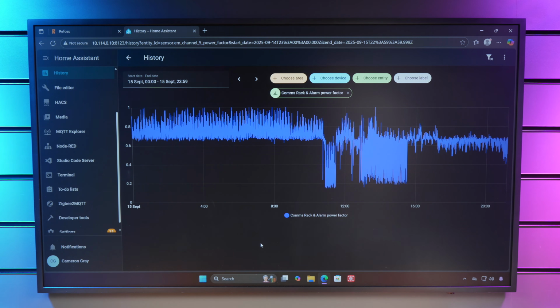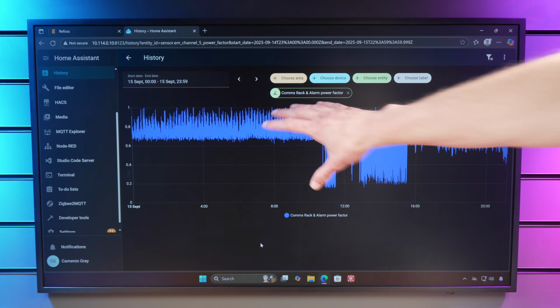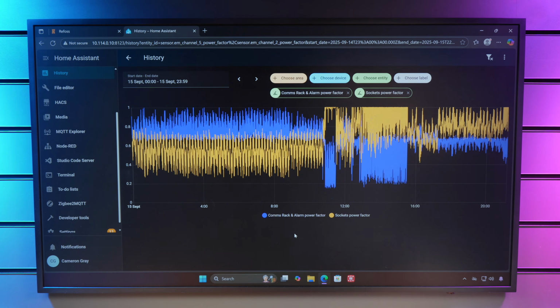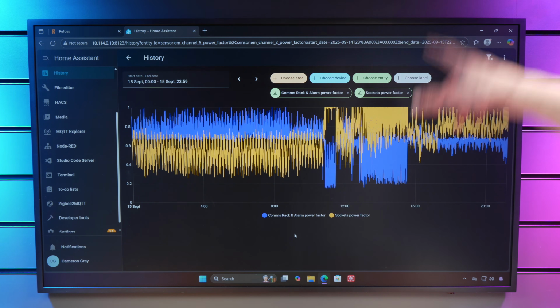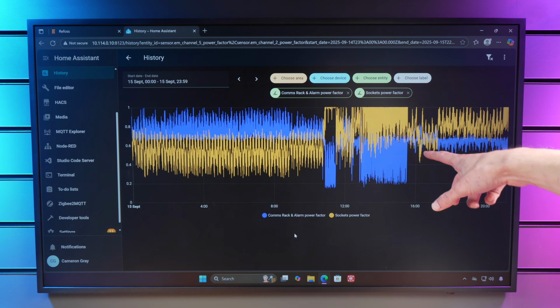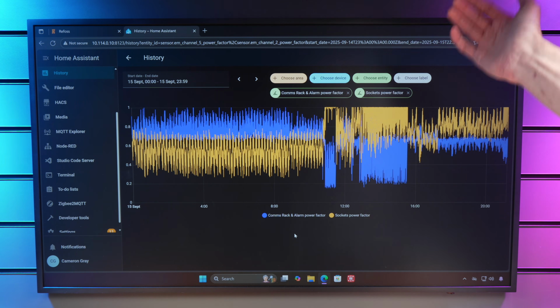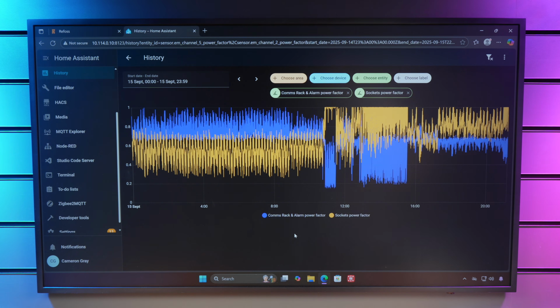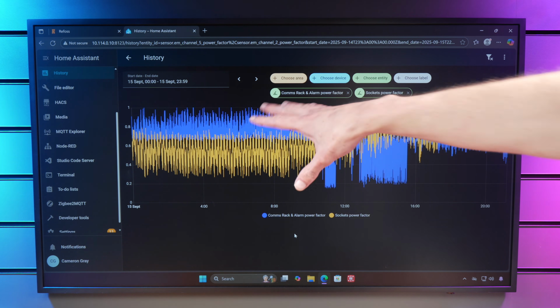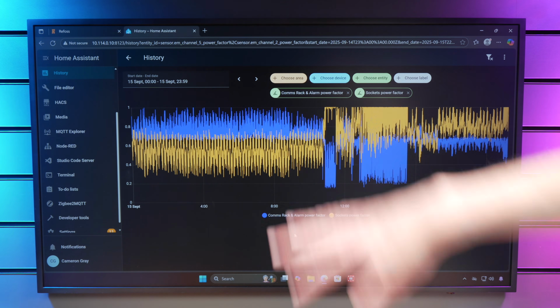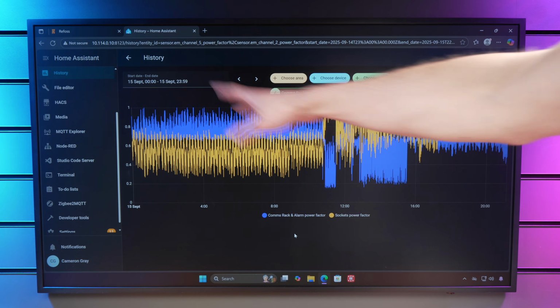But it gets even weirder, because this is the power factor just for the comms rack circuit, and now overlaid on top is the power factor for my socket circuit. So the blue is the comms rack circuit, the orange is the power factor for the socket circuit. And you can see a weird interaction between the two. Both of these are experiencing pretty weird fluctuations the whole time.